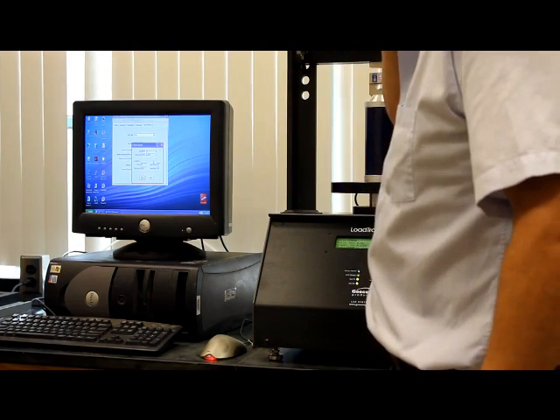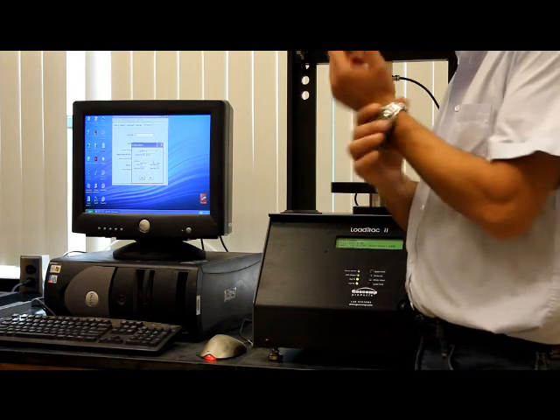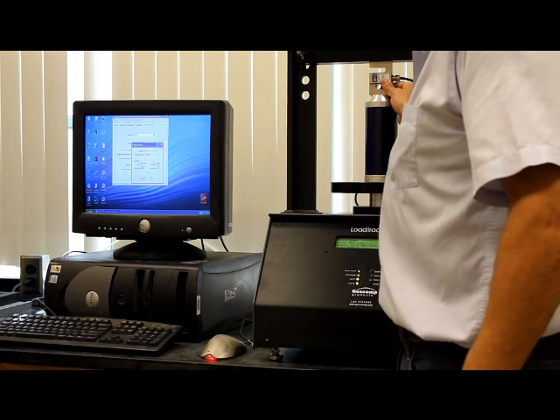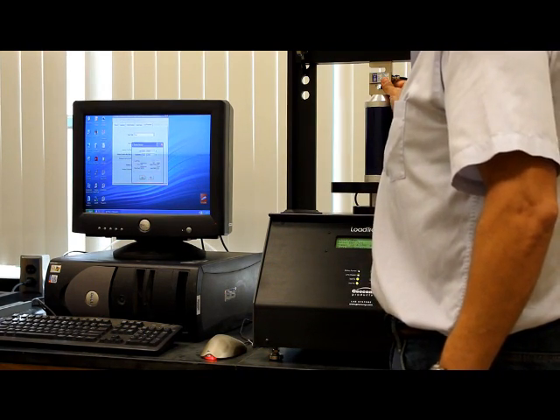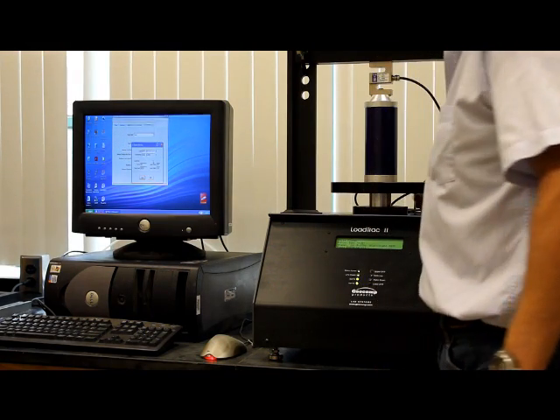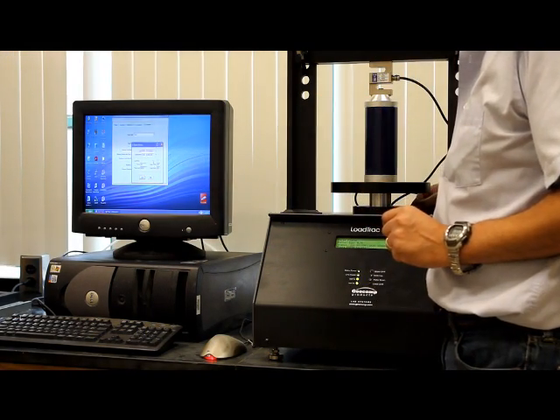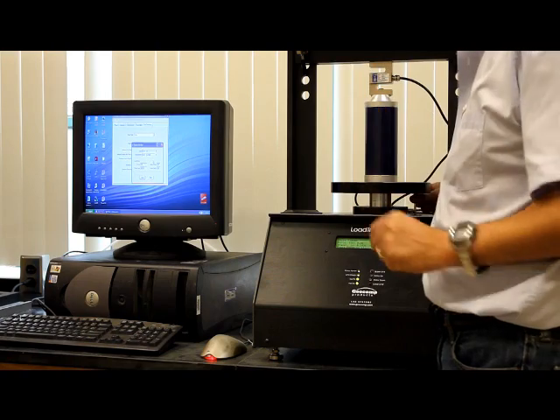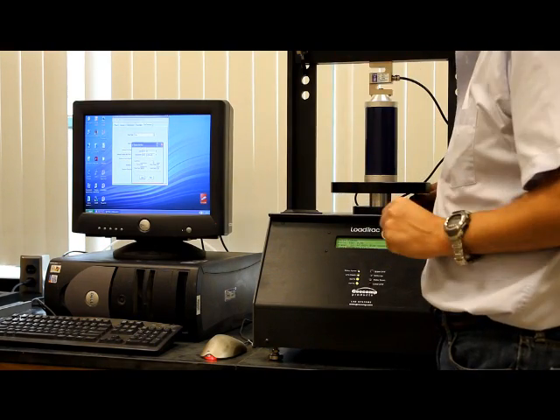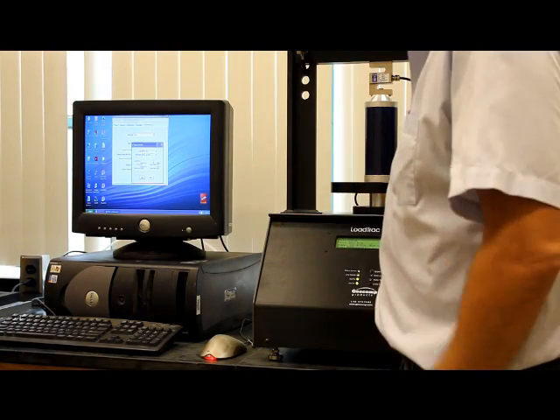One last check that you can do, if you are not sure. You can press on the load cell and you should see about 20 pounds. And displacement, if you have a gauge, you can move it with a known thickness and you should move by the same. That means your calibration is okay.